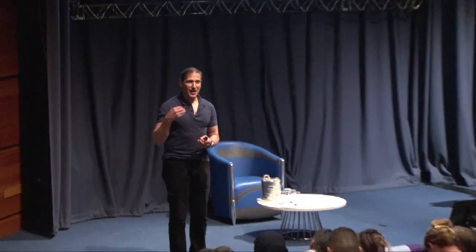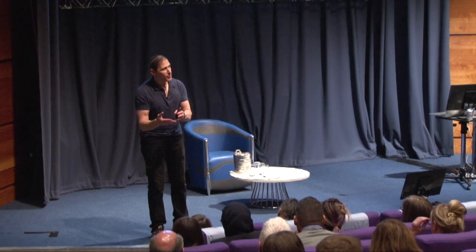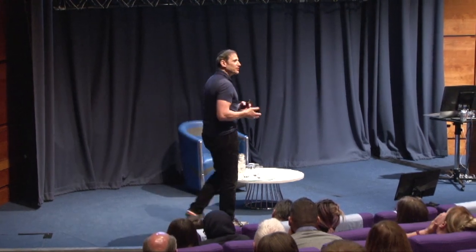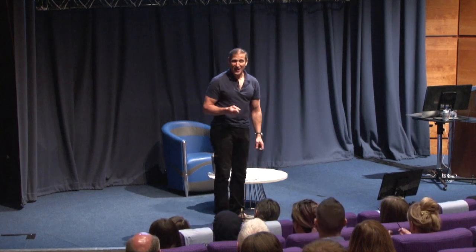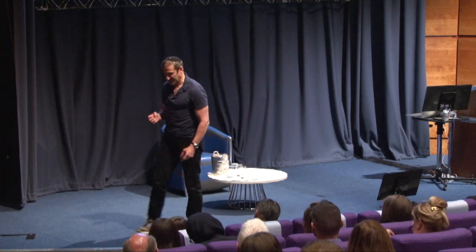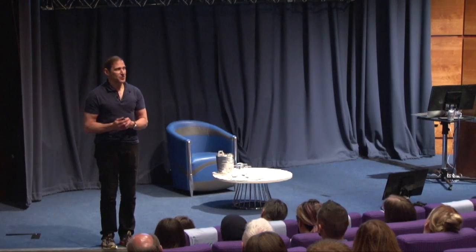We were talking about radio frequency burns, and we said that in a sense you had to think like an electron as to where the oscillating magnetic field that you irradiate the patient with, where would the induced electrical fields cause an electron to wish to flow, as it were, as it creates its own circuit. So think of path of least resistance, and I think you'll be in good shape.